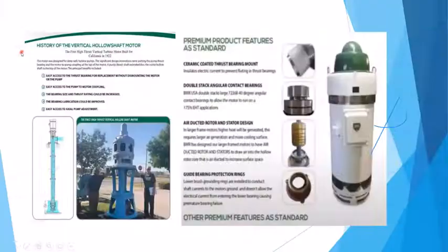The other factor, and this is actually Dennis Grimmel, he was with BMR until, sad to say, I lost him about a year ago. He had 50 years of experience in vertical turbine technology. What I see on a lot of pumps is they all talk about the new VFD type motors, because of that static noise. It's about 100 horsepower and up, you see it more often than in smaller motors.